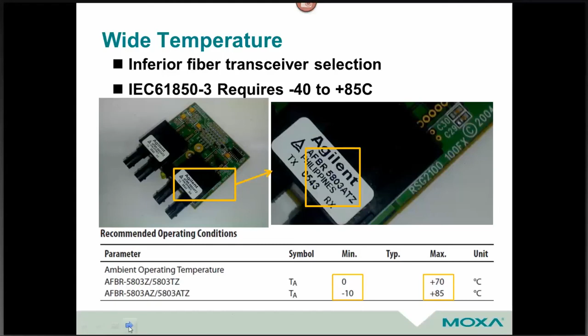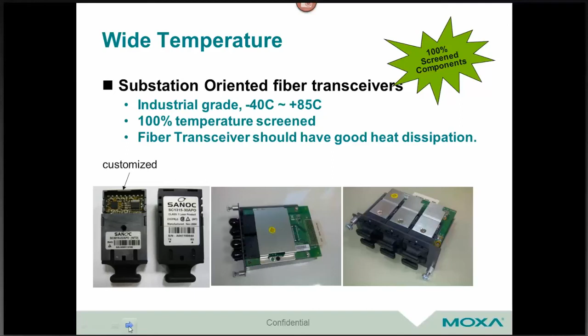So here's a picture of a product that does not comply with it because you can see the temperature range of the actual fiber transceiver, a very critical component in the communications, is not compliant with the standard. And so it's kind of strange how the product got to be certified, but it's always good to check to see, was it built from the ground up? Were these nasty environments taken into consideration? If you look at the difference in our transceivers here, or a good transceiver I should say, you'll see that heat sinks are really required on anything fiber to make sure that they are transmitting and receiving in very hot temperatures and will be stable. So it's always good to look for those types of things within a product.